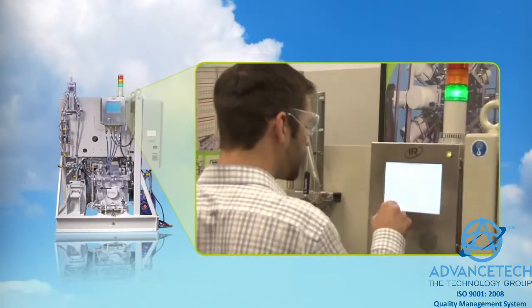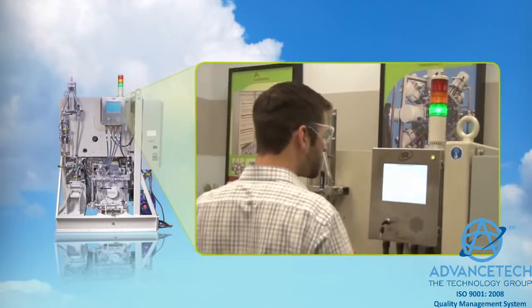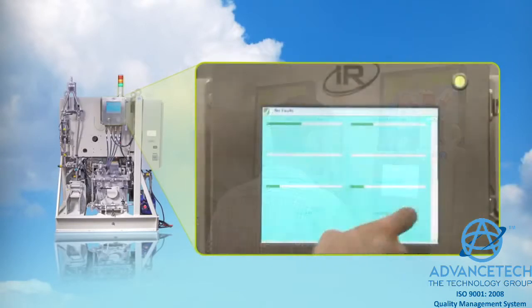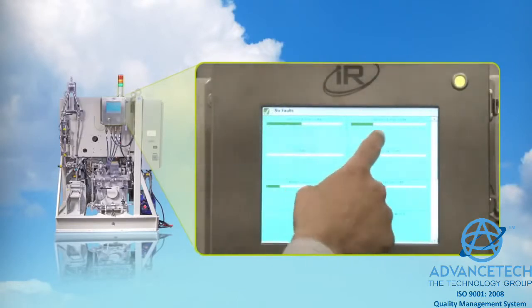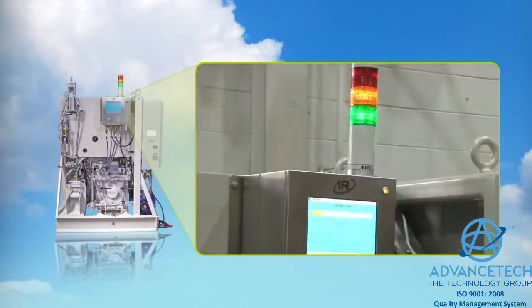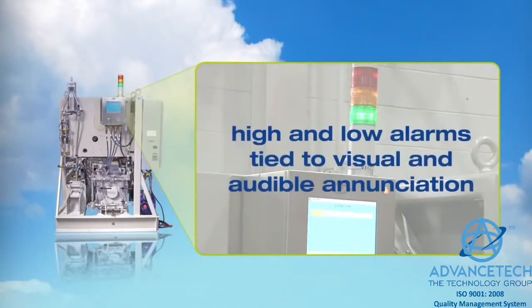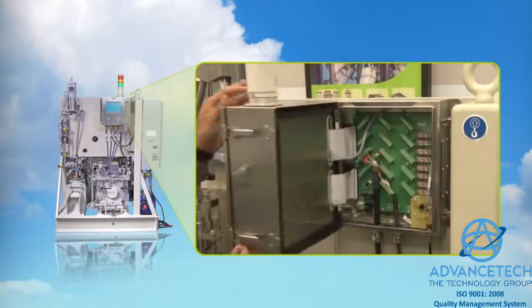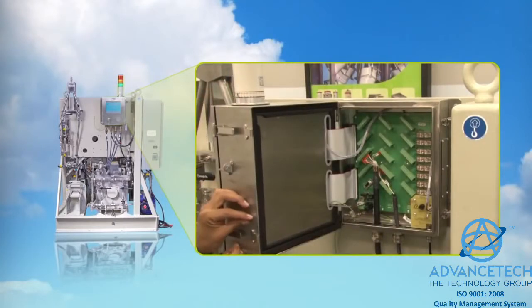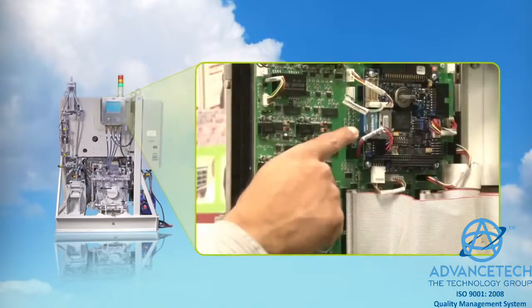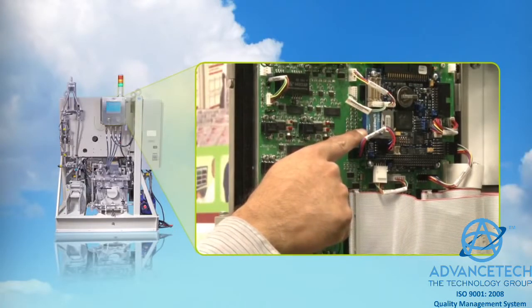All detector and sample process inputs are fed into the IR7040 intelligent rate meter. Each input is configured as a virtual channel for display, and each virtual channel has the capability to provide high and low alarms, which can be tied to visual and audible annunciation. The IR7040 also provides dry contact safety rated relays and digital outputs for remote annunciation.